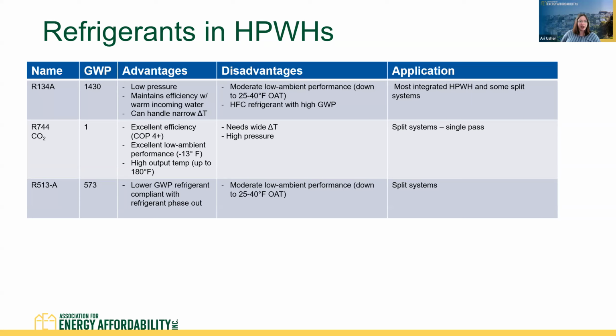R744 is actually carbon dioxide. This is going to be in split systems and single pass systems. It has excellent efficiency, does really well, and also performs really well even in low ambient temperature environments. And then we've got R513A, typically in split systems. This is a lower global warming potential refrigerant, compliant with any upcoming refrigerant phase-outs. We'll go more into the equipment options and which refrigerants they use in a bit.